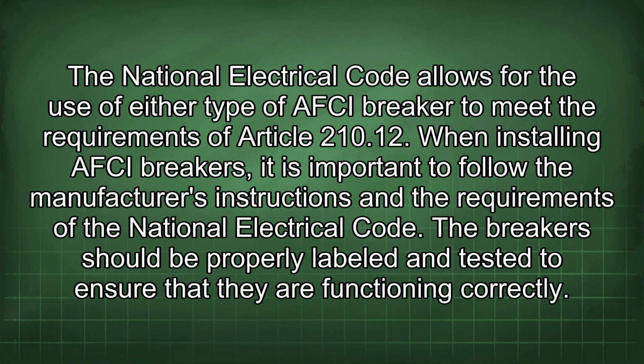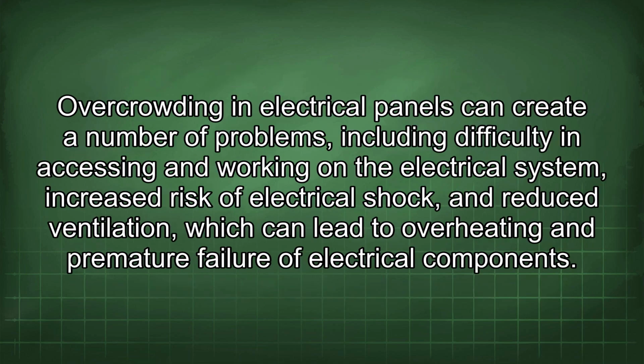of Article 210.12. When installing AFCI breakers, it is important to follow the manufacturer's instructions and the requirements of the National Electrical Code. The breakers should be properly labeled and tested to ensure that they are functioning correctly. Overcrowding in electrical panels can create a number of problems, including difficulty in accessing and working on the electrical system, increased risk of electrical shock, and reduced ventilation, which can lead to overheating and premature failure of electrical components.